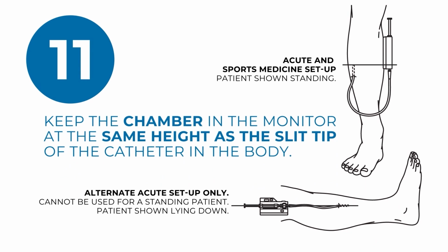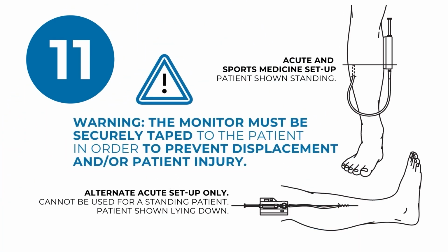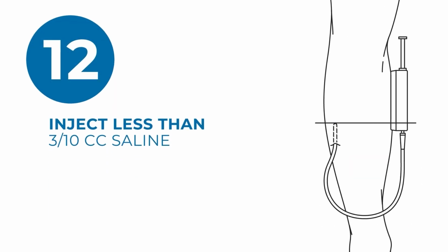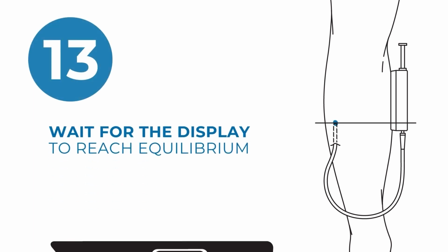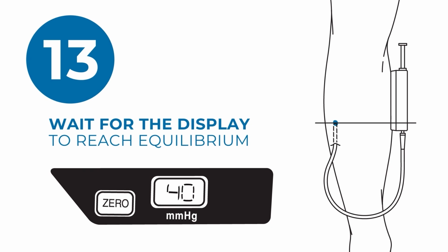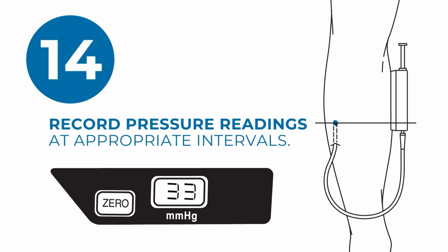Keep the chamber in the monitor at the same height as the estimated height of the slit tip of the catheter in the body. The monitor must be securely taped to the patient to prevent displacement or patient injury. Now, slowly inject less than 0.3 cc saline into the compartment to equilibrate with interstitial fluids. Wait for the display to reach equilibrium. Then, read and record pressure readings at appropriate intervals. Repeat steps 12 and 13 to ensure patency for subsequent measurements.